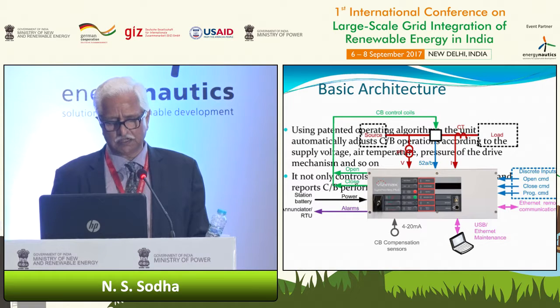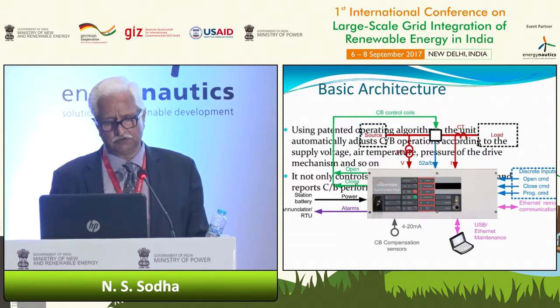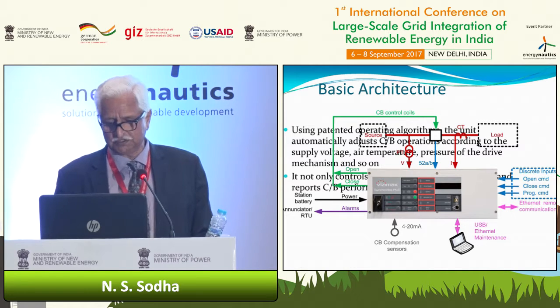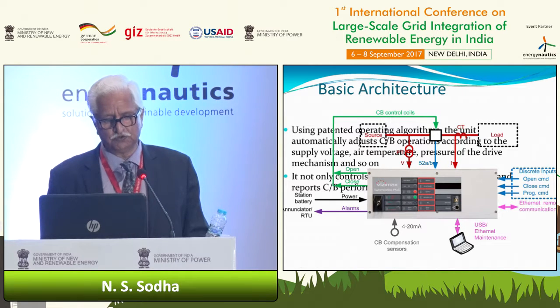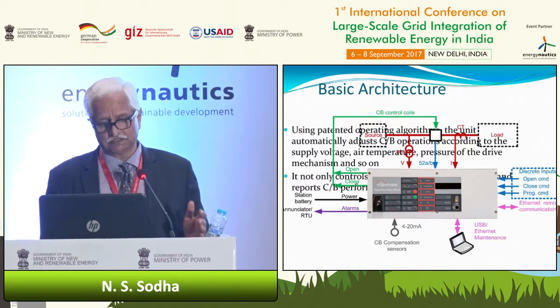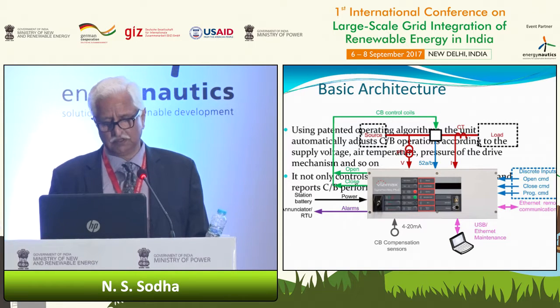Now the basic architecture uses a patented operating algorithm. The unit automatically adjusts circuit breaker operations according to the supply voltage, air temperature, pressure of the drive mechanism, and so on. It not only controls the circuit breaker switching, it also monitors and reports circuit breaker performance problems and alarms. So it works as online equipment which gives you feedback about the breakers.